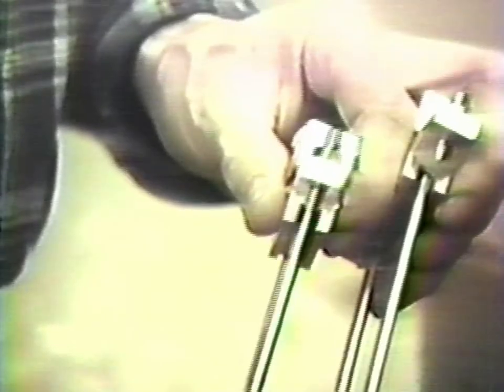The box containing the rest of the small parts can now be opened. Included are two stirrups or suspensions from which the sample pans are hung. Remove the packing material from the stirrups. Note that the stirrups are marked with one dot for left and two dots for right.